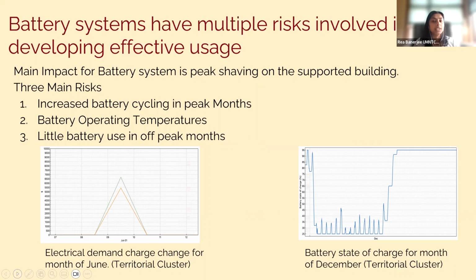All batteries will be mainly used for peak shaving on the supported buildings. There is some risk involved with battery systems: batteries will be overused in peak months and underused in off-peak months, according to the SAM model. On the right is the lack of use during December for the Territorial Hall cluster, which results in battery degradation since the battery isn't cycling during that time. Battery operating temperature is another risk—some of the larger batteries will be placed outside, which in Minnesota temperatures could lead to more unforeseen battery degradation and cell loss.